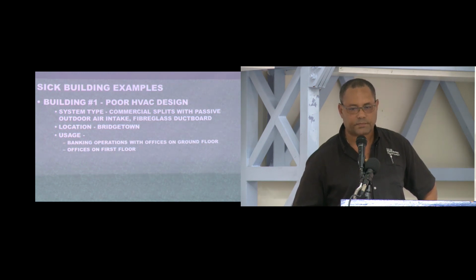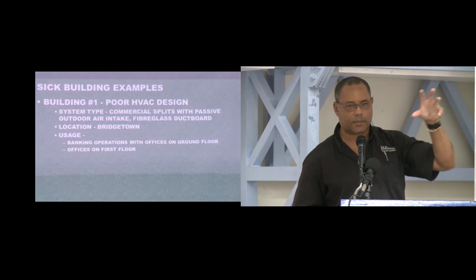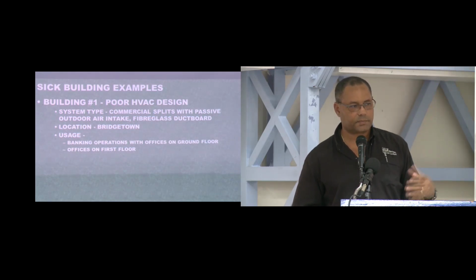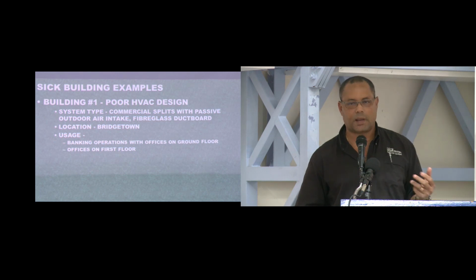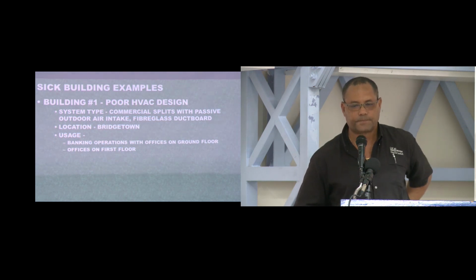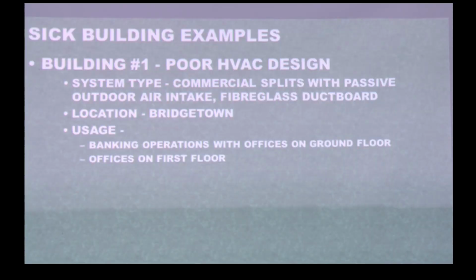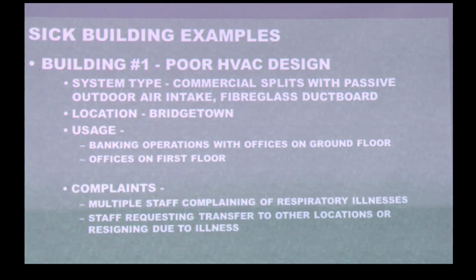Commercial split system, a passive outdoor air intake. There's a duct running down from the roof, branches off to a couple of plant rooms, and the system is supposed to suck air in through that duct. A banking operation with offices on the ground floor and offices on the first floor. People complaining of respiratory illness, staff requesting transfers or resigning. So quite significant impact.